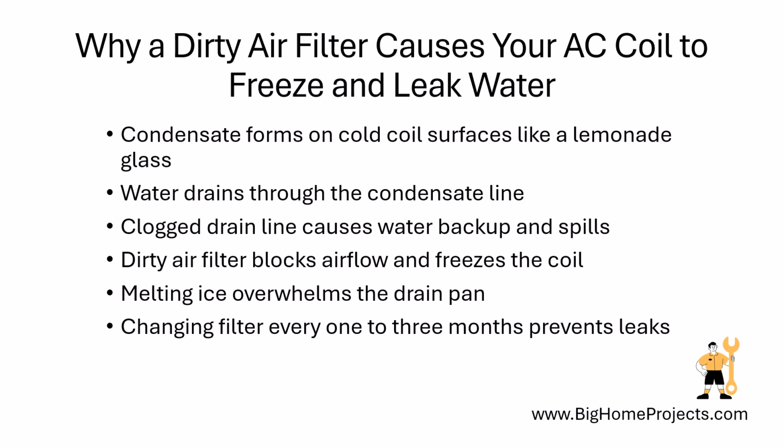Something a lot of people do not know is that a dirty air filter is one of the sneakiest causes of leaks because it blocks airflow, makes the coil inside get too cold, and causes ice to build up. When that ice melts, it melts faster than the drain pan can handle, and boom, you get a puddle. Changing that filter every 1 to 3 months can honestly prevent most of these headaches before they even start.